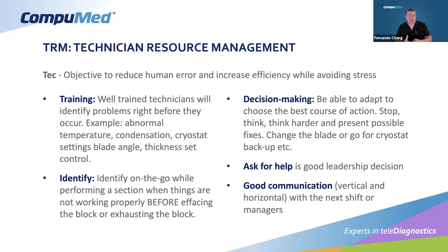And also for decision making at the managerial level, we need to have perhaps a different schedule of preventive maintenance. Some places do yearly preventive maintenance, and perhaps we need to have a 6 month preventive maintenance, because preventive maintenance is going to discover many things. While one cryostat, that's what I always said, have two cryostats. One cryostat is being maintained. Then this cryostat is going to be unplugged.